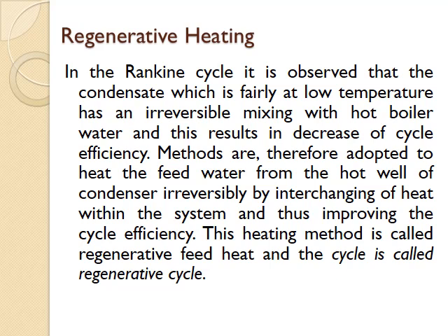Methods are therefore adopted to heat the feed water from the hot well of the condenser by interchanging of heat within the system, and thus improving the cycle efficiency. This heating method is called regenerative feed heating, and the cycle is called regenerative cycle.